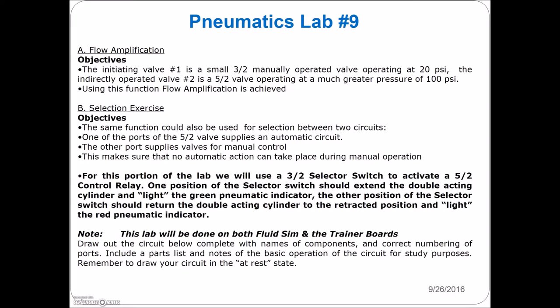Alright guys, pneumatics lab number nine. I've tried to simplify this but I wanted to get two things in — the fact that you can do this for a flow amplification application or you could use this for a selection exercise. All we're doing is we're going to have a 3/2 controlling a 5/2. The initiating valve one is a small 3/2 push button operating at around 20 psi, and the indirectly operating valve — the 5/2 that it's controlling — is at a much greater pressure of 100 psi.